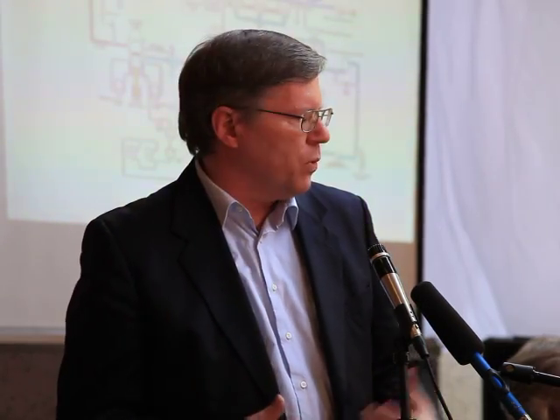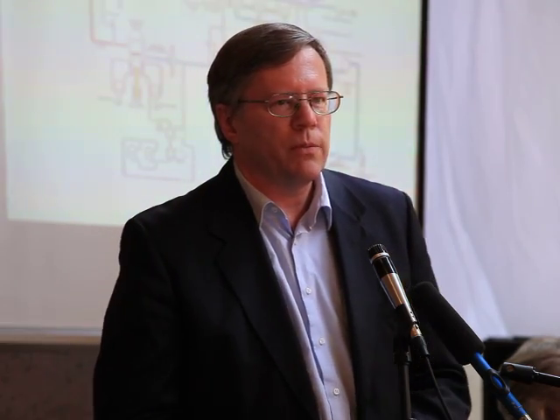About a minute later, the turbine tripped — there wasn't enough steam going through it anymore. The earthquake had knocked out the electrical grid, the normal source of power to the plant. When the turbine tripped, the generator tripped, meaning it wasn't producing any electricity for the plant either. So both the earthquake and the turbine trip took away the normal source of power for the plant.